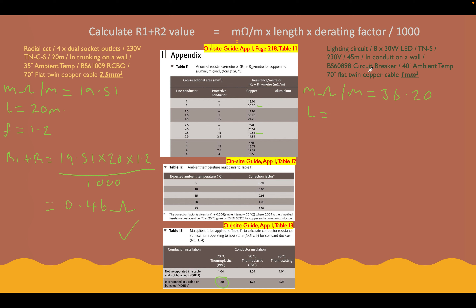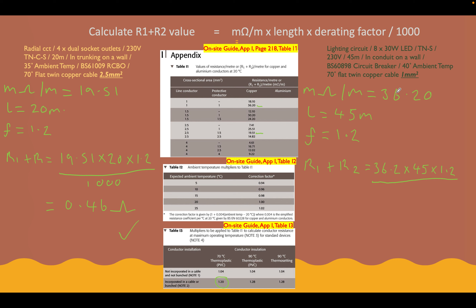The length of our circuit is 45 metres. The last thing we need is our factor. Same again — we're going to choose the worst-case scenario. Same type of cable, protective conductor incorporated in the cable, so we're going to use a factor of 1.2. Our R1+R2 for the lighting circuit is therefore 36.2 × 45 × 1.2 ÷ 1,000, which gives us a value of 1.95 ohms.